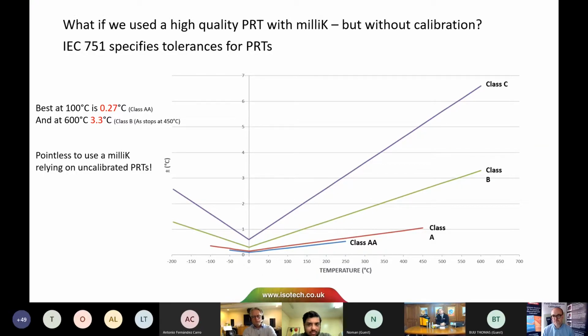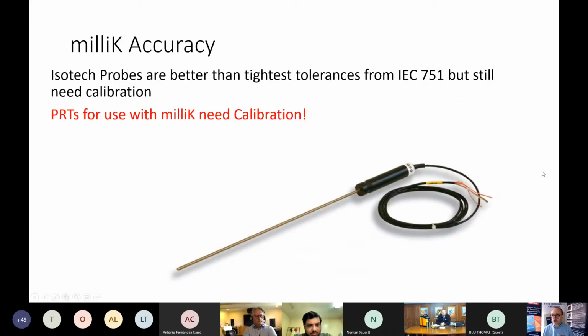So that's not great for us, and it's pointless to use a milliK if the PRTs aren't calibrated, because we'll have the high accuracy for the milliK, sure, but the tolerances on the PRTs will be so poor that we're not getting a good measurement. So our probes are better than the tightest tolerances from IEC 751, but they still need calibration. So PRTs for use with the milliK need calibration.